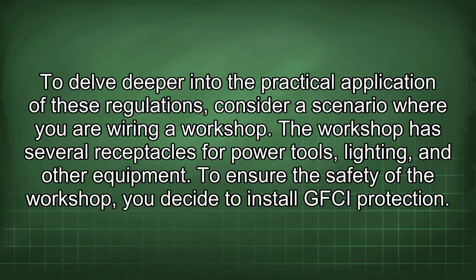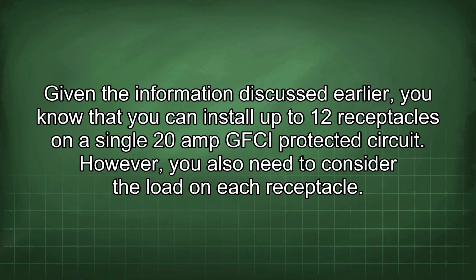To delve deeper into the practical application of these regulations, consider a scenario where you are wiring a workshop. The workshop has several receptacles for power tools, lighting, and other equipment. To ensure the safety of the workshop, you decide to install GFCI protection. Given the information discussed earlier, you know that you can install up to 12 receptacles on a single 20 amp GFCI protected circuit. However, you also need to consider the load on each receptacle.